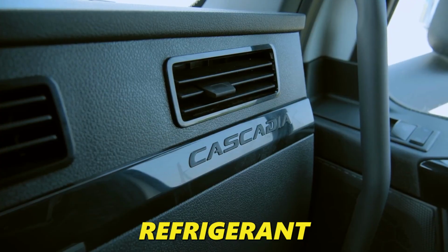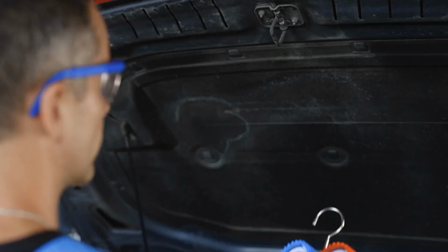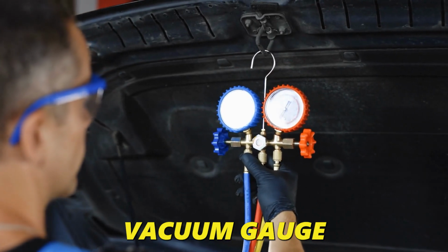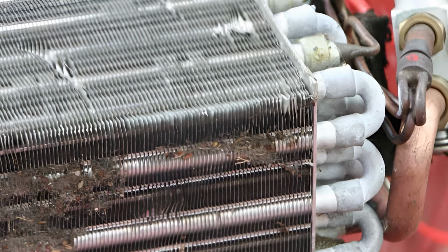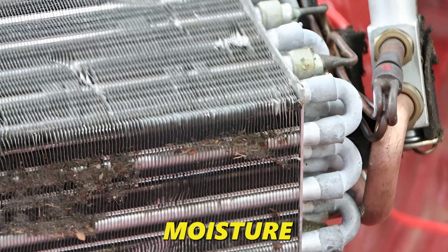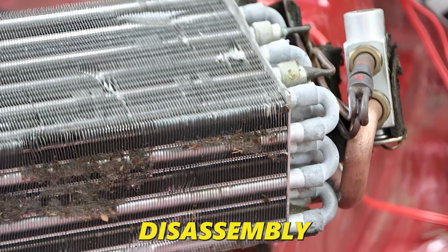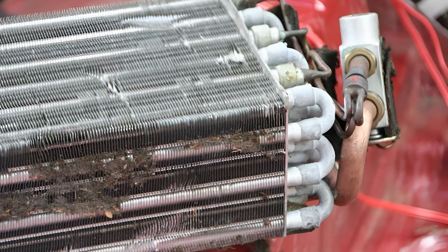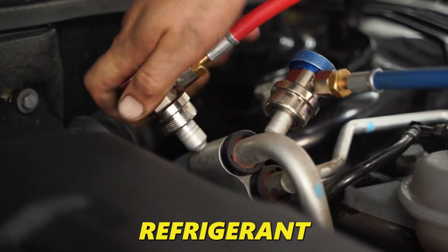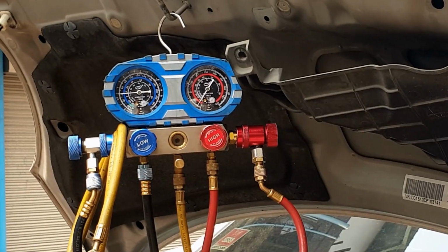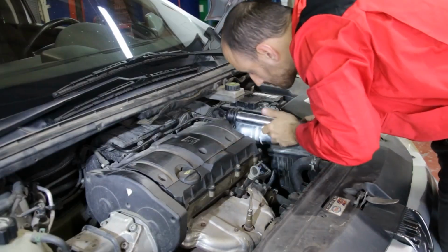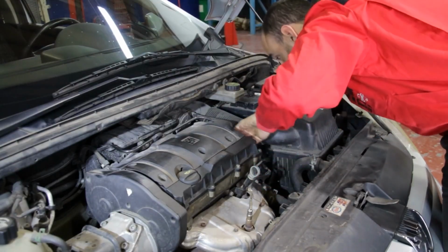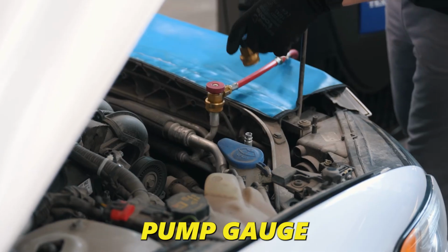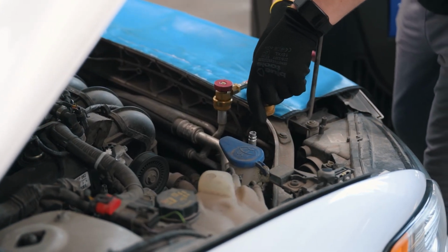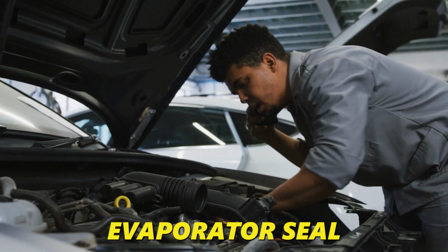Before we add any refrigerant, we pull a deep vacuum on the system. We're targeting 500 microns or below on the vacuum gauge. This does two things. First, it boils off any moisture that entered the system during disassembly, because moisture in a refrigerant circuit forms acids that destroy your compressor and expansion valve. Second, it confirms the system holds vacuum before we put refrigerant in. If the vacuum rises after we isolate the pump, we have a leak. We find it now, not after charging. 490 microns. We isolate the pump. Gauge is stable. The system is holding. That evaporator seal is good.